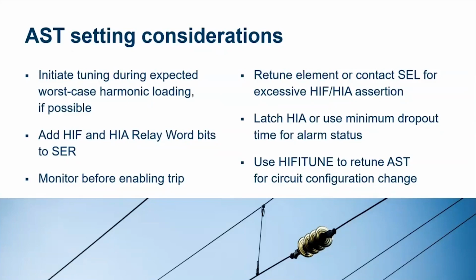So we looked at ways to qualify before, with a high impedance fault detection with a potential open phase condition. There are other bits and other methods that we can use to qualify a high impedance fault assertion to give us a higher degree of confidence that it is associated with a down conductor. It just depends on what information you have available. So really, it's going to depend on the specifics of your system, where it's applied, and the different devices and comms that you have available. But once again, we're more than happy to discuss and see what makes the most sense for your system.